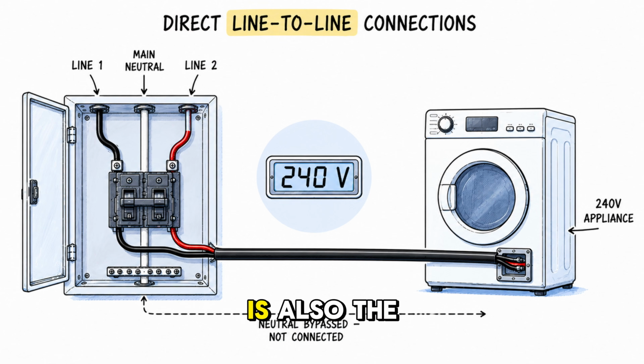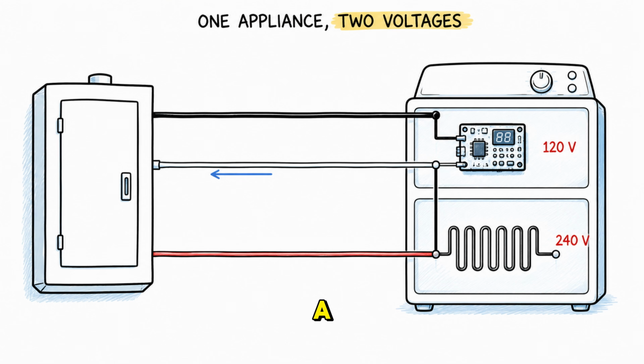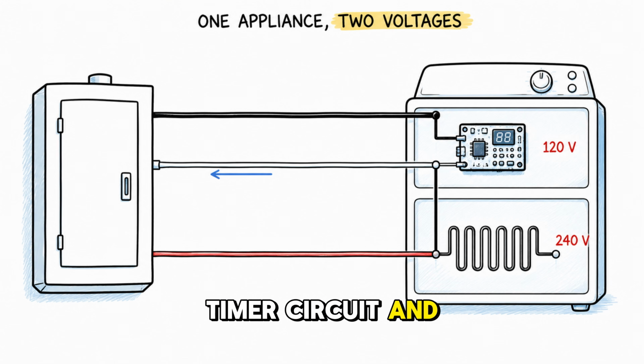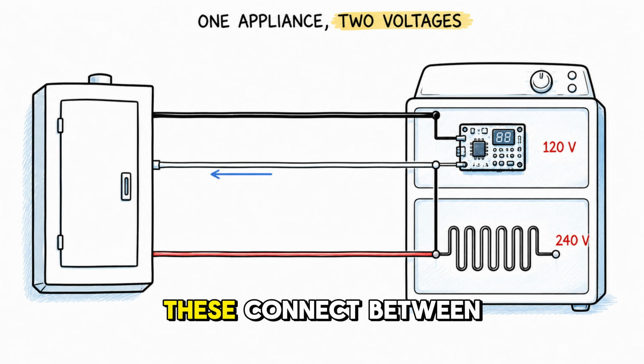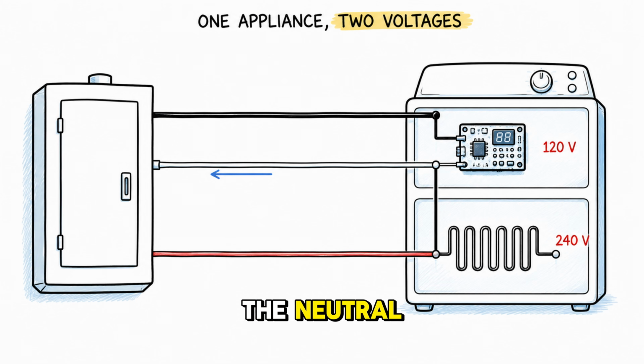The neutral wire is also the reason your heavy 240-volt appliances work. A dryer motor or heater needs 240 volts, so it connects directly between line 1 and line 2. But that same appliance also has a 120-volt timer circuit and digital control board. These connect between line 1 and the neutral. Both voltages come from the same panel, utilizing the same neutral wire as the return path for the electronics.